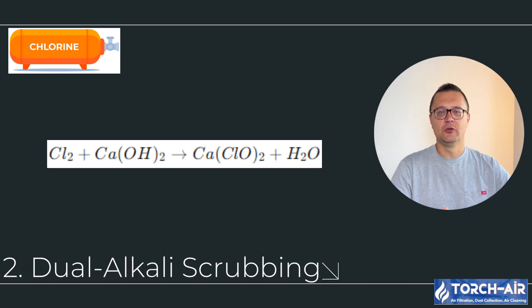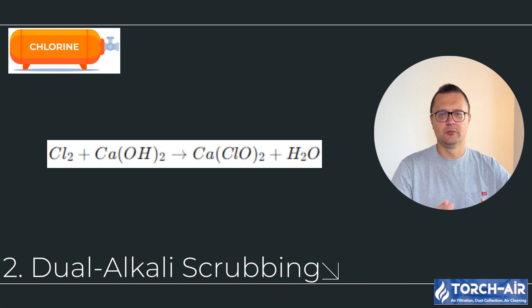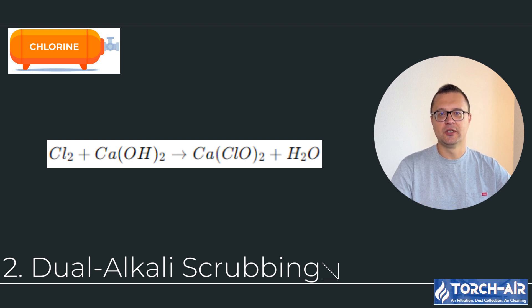The second technique is dual alkali scrubbing. In some cases, using a combination of NaOH and calcium hydroxide — Ca(OH)2, or lime — enhances chlorine neutralization. This dual alkali system is highly efficient for capturing both chlorine gas and other acidic gases simultaneously. The process is similar to wet scrubbing, but the lime slurry enhances the neutralization process. This is particularly useful when dealing with complex emissions that contain multiple contaminants. Best for industrial setups with mixed gases or where high chlorine concentrations are common.